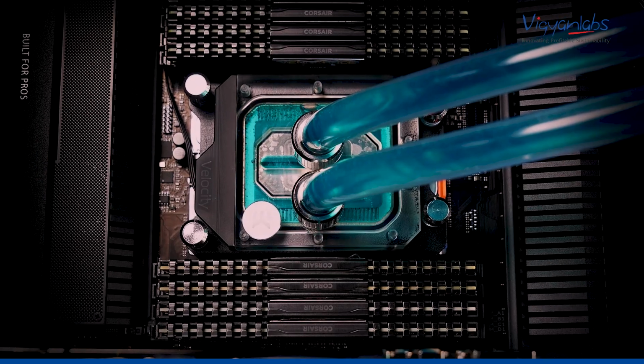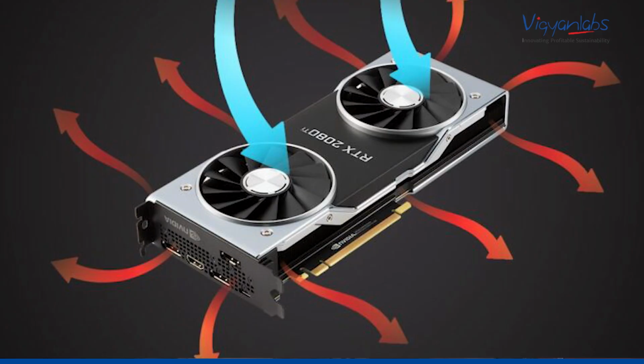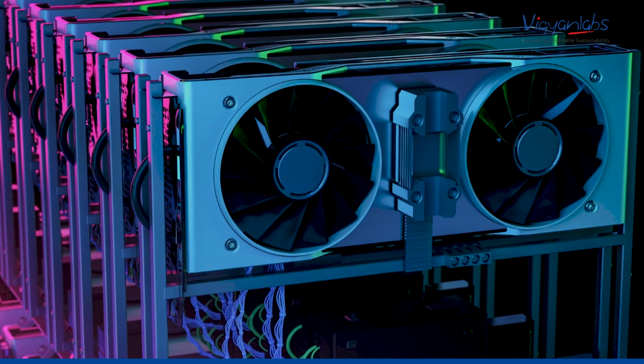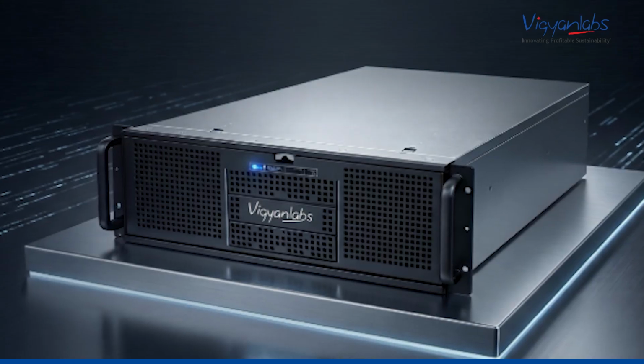When it comes to GPU workloads, is liquid cooling mandatory? I think liquid cooling is not mandatory. As long as the power envelope of a rack is less than 30 kilowatts, you can do with a combination of air cooling and other indoor cooling techniques. You don't need liquid cooling. The moment you cross 40 kilowatts, liquid cooling becomes mandatory. Femto is designed to work in an air cooled environment. Starting from 500 watts to 5 kilowatts, you have different versions of Femto which can run with a low power envelope.